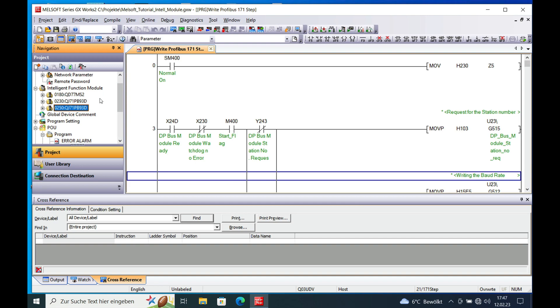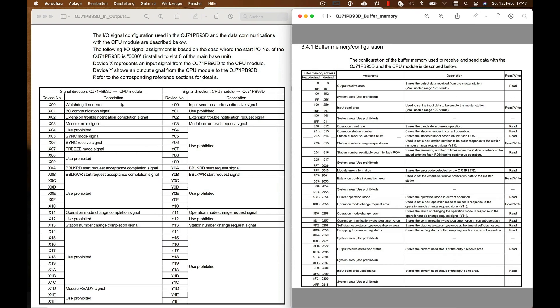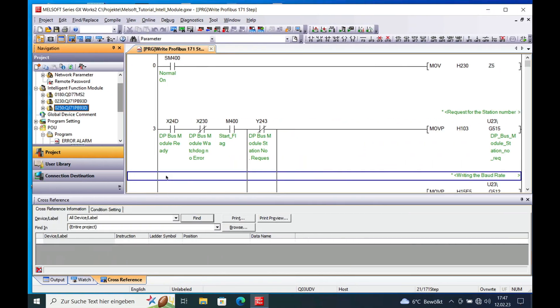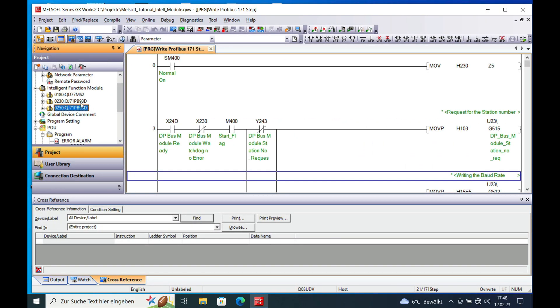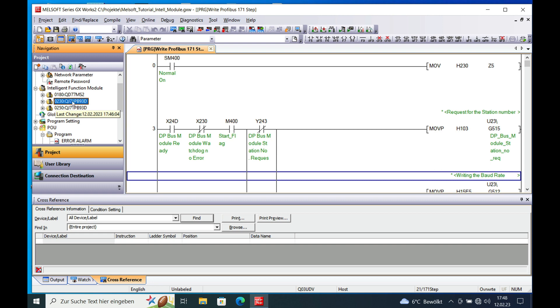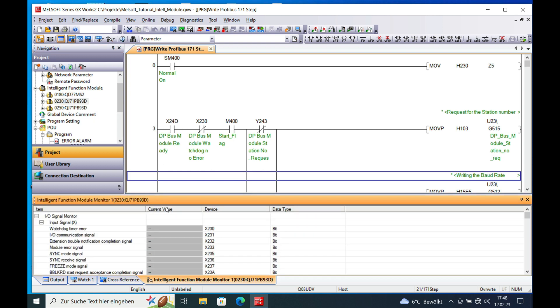And another thing is if you do not have this document handy, it will be very easy. Because you can just go ahead and go to your module that we first put in with the address number 230 and make a right click on there. And then you can register this to your Intelligent Function Module Monitor. Click this and you will see all your addresses already being provided right here.